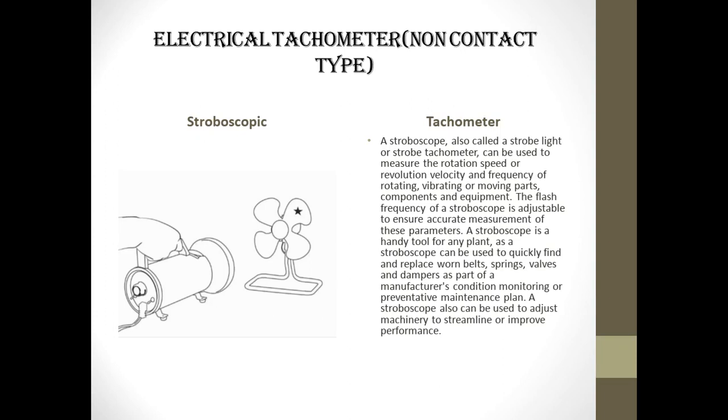Disadvantages: the circuit of the variable frequency oscillator cannot be stabilized to a given fixed frequency. Therefore, this method is less accurate than the method utilizing digital meters. Number 2, the stroboscope cannot be used in surroundings where the ambient light is above a certain level. The stroboscope requires subdued lighting conditions for efficient operation. Commercially available stroboscopes are usually found in the range of 600 to 20,000 rpm.